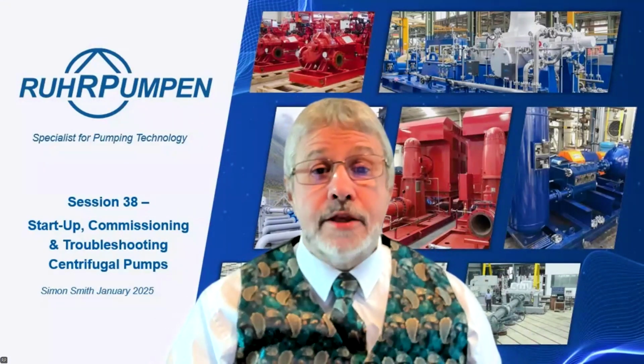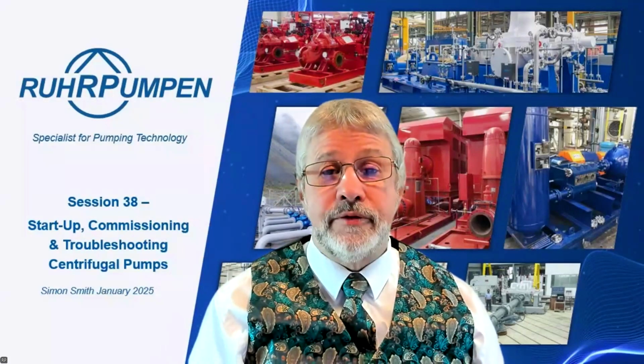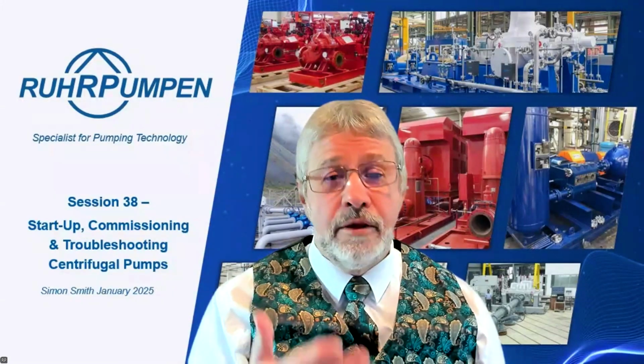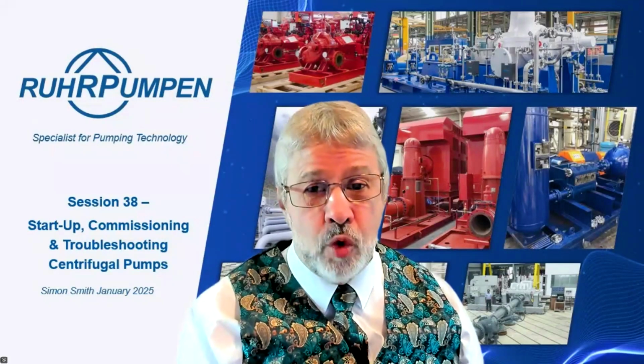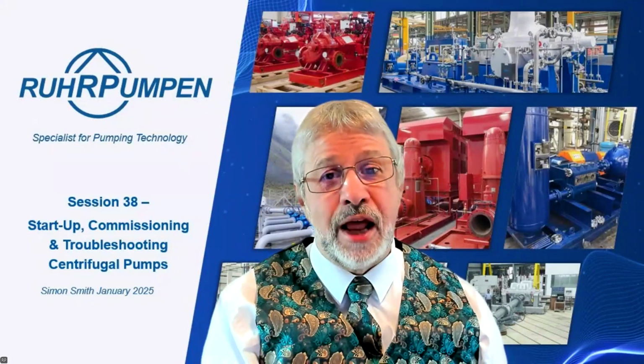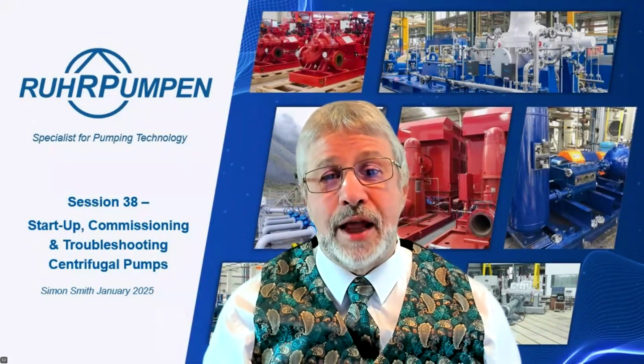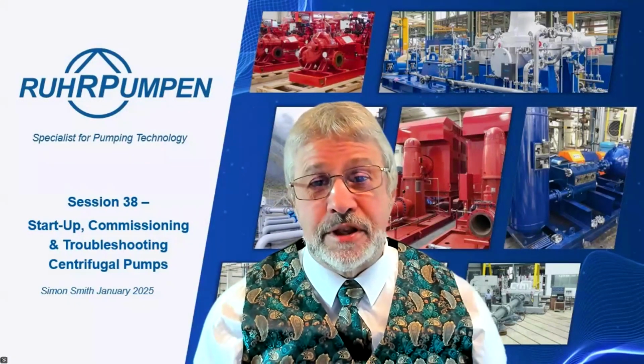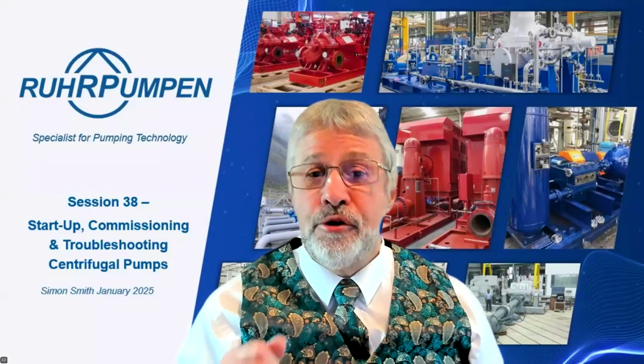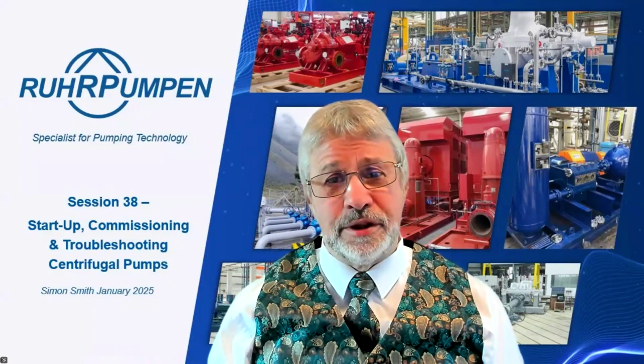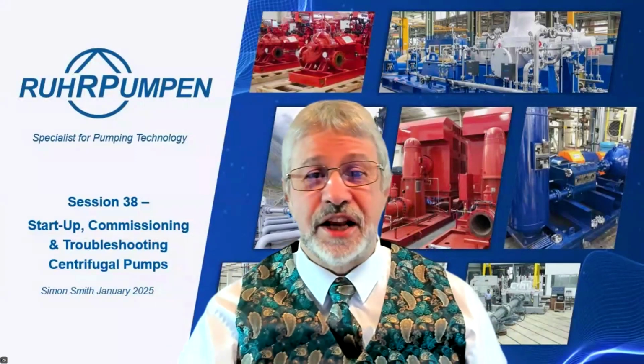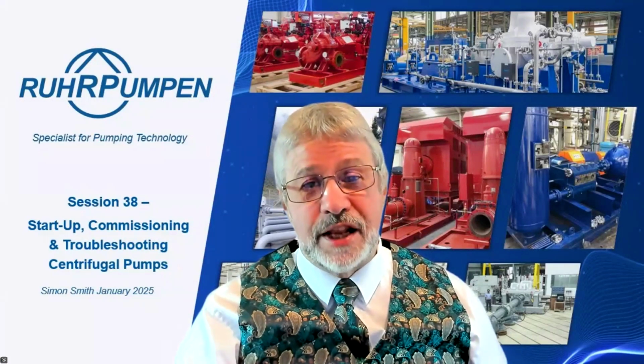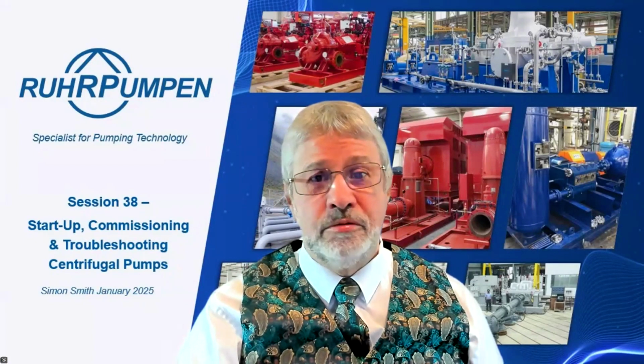What precautions do we need to keep in mind when we're commissioning hot service pumps? Key thing is going to be warming it up properly. If it's a hot service pump, if you're talking about 200, 300 degrees centigrade, it's critical that you follow the manufacturer's recommendations. They will tell you in detail in the IOM how to run the hot fluid through the pump and at what rate, usually through the drain connection, out through the vent connection or the discharge connection. They'll tell you how quickly to do it, and how to make sure it reaches other parts, maybe through the mechanical seal as well, to make sure that it's all gradual. Follow the IOM. The general rule is it's going to come in through the drain connection, and out through the vent connection, or out through the discharge connection, at about 40 degrees centigrade per hour until it gets up to temperature.